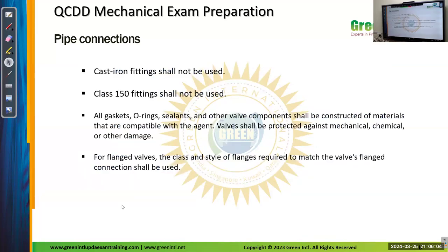So cast iron is not permitted. Class 150 fittings are not permitted. And gaskets, O-rings, sealants, and other valve components shall be constructed of materials that are compatible with the agent. We have to make sure that this does not chemically react with the agent. Valves shall be protected in accordance with the components. All flanged valves and class types of valves required to match the valve's flanged connection shall be used.